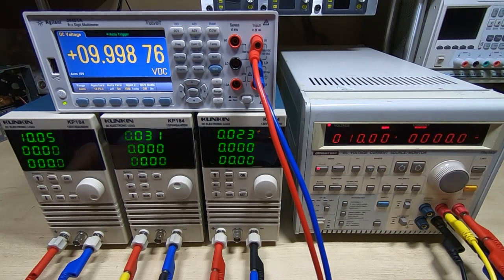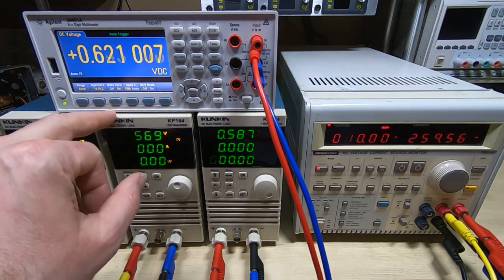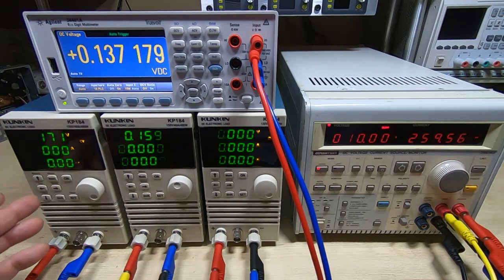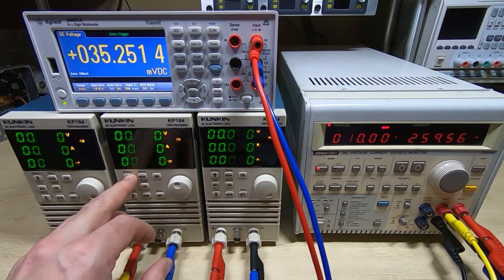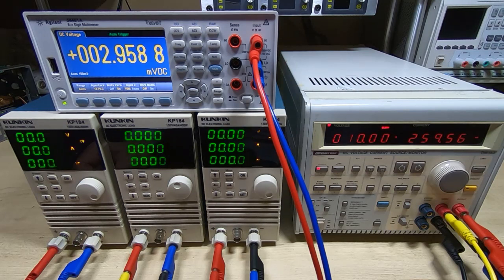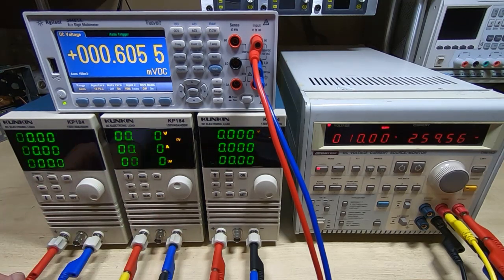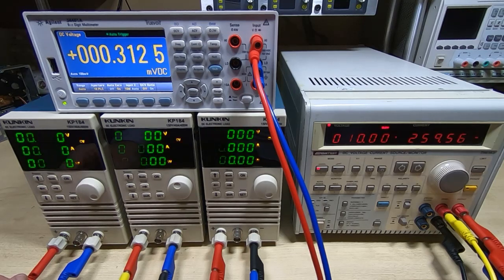So step one, turn the source off and we need to put these into calibration mode. As I said, to do that you turn them off, hold the up arrow, power them back on, and they should come up with the first message on the screen showing that they are in the first voltage calibration point.